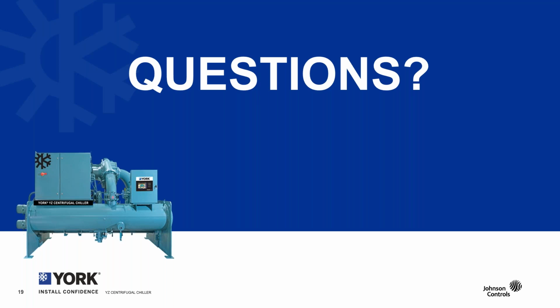It's a low pressure refrigerant. So does the YZ incorporate a purge unit? Can you tell us a little bit about the purge? Yes, with any low pressure refrigerant that has the possibility of operating less than atmospheric pressure, which we do, if there was ever to be a leak, it could allow air into the machine as opposed to leaking out. ASHRAE and other codes and standards require that, and we think it's the right thing for our customer to provide that, so we will have a purge unit as a standard feature of the YZ chiller. It's a purge unit designed by the team here at York, integrated into our OptiView control system, and it's a very seamless portion of the chiller design.